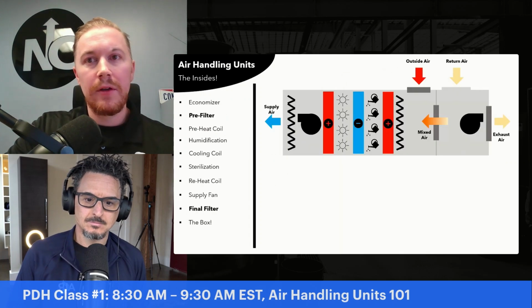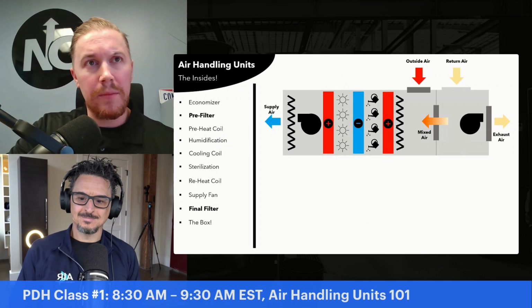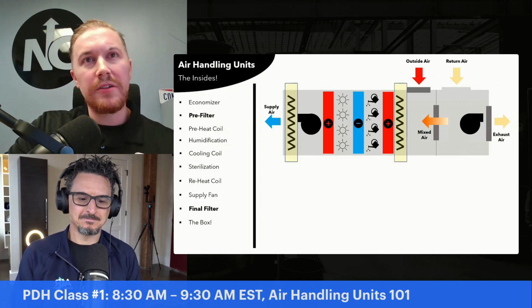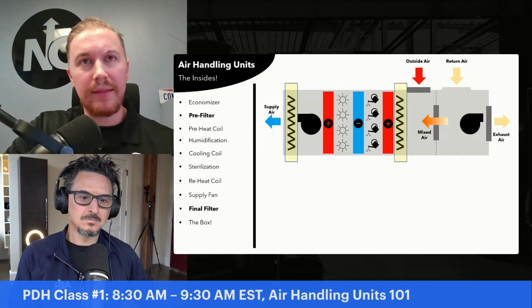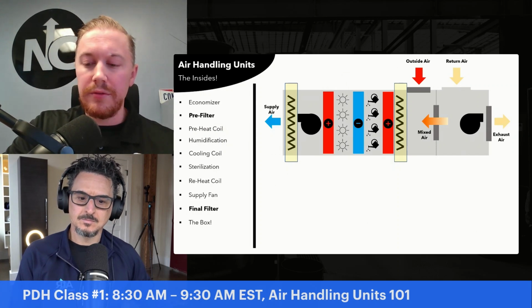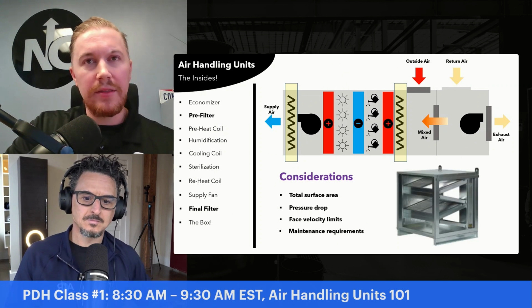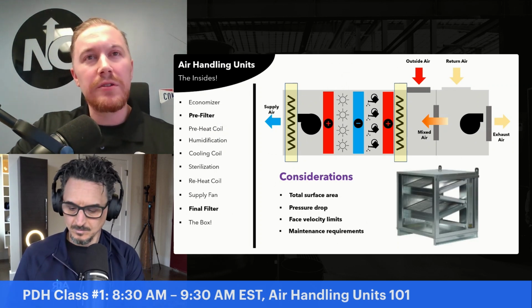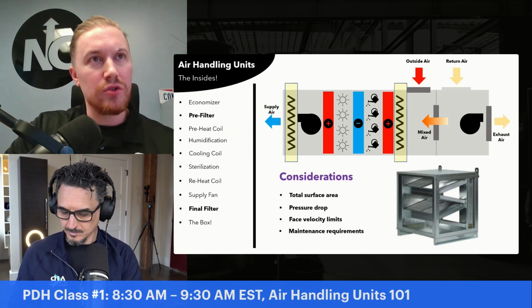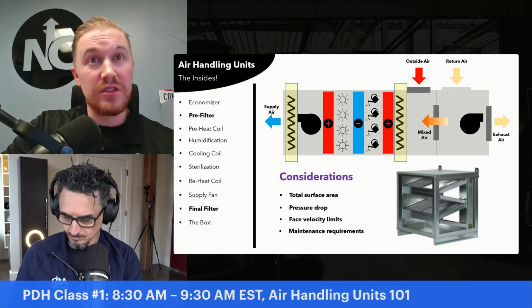Okay. All right, great. So we're moving towards the end here. I'm going to move pretty fast because I know we're coming up on time. So what else do we see in the air handling unit? And these will just be very high level summaries of these components. Well, we see filters. Okay. And the takeaway for a new engineer in the space is filters need to have controlled pressure drops and face velocities, just like coils.